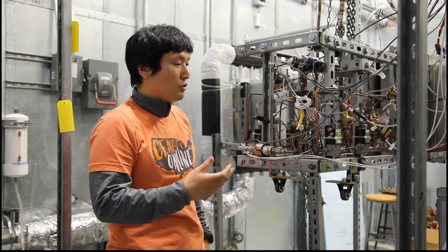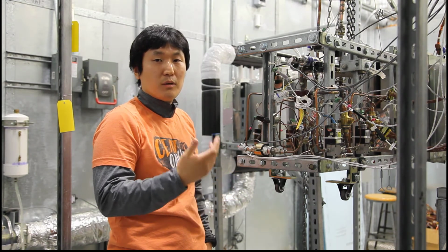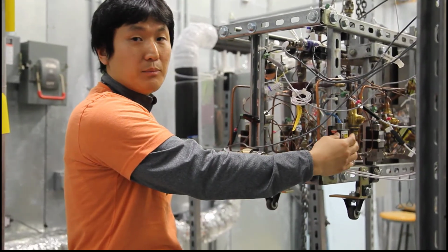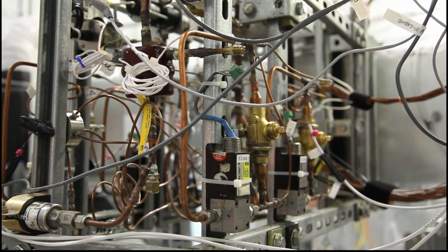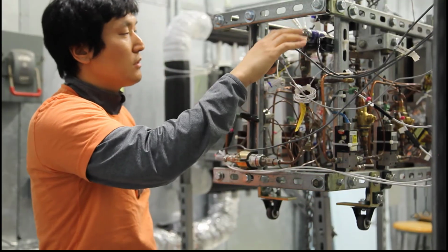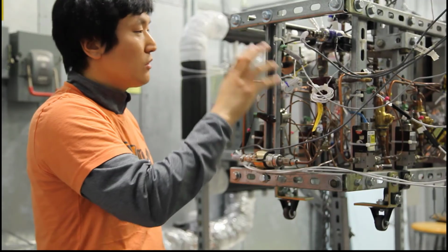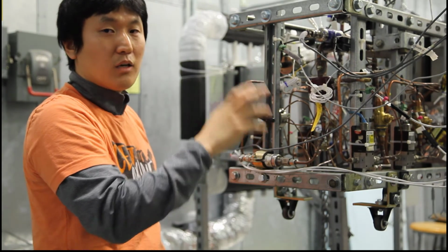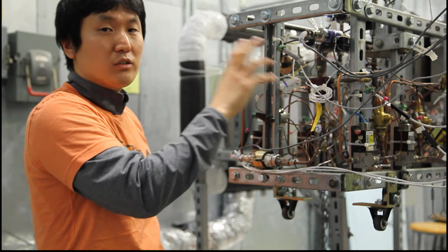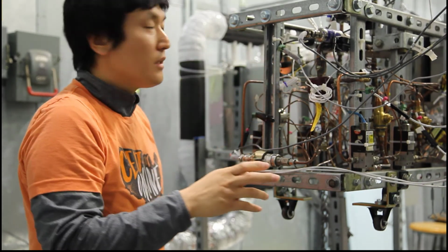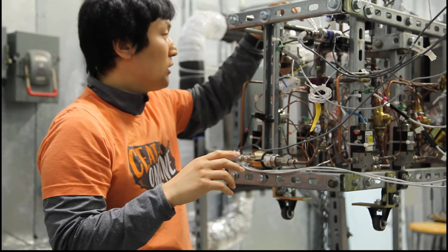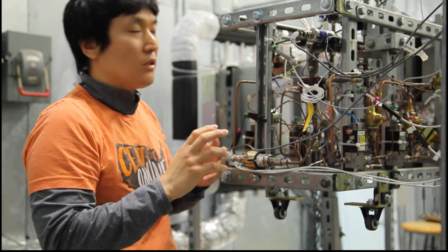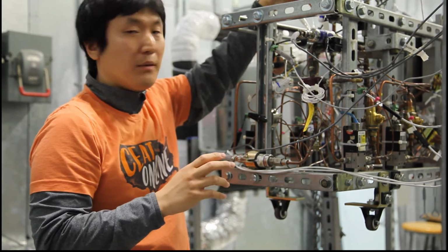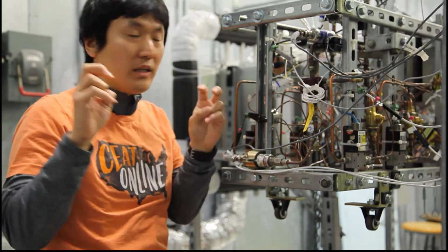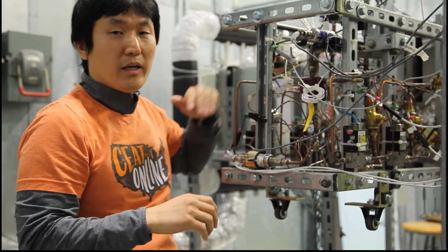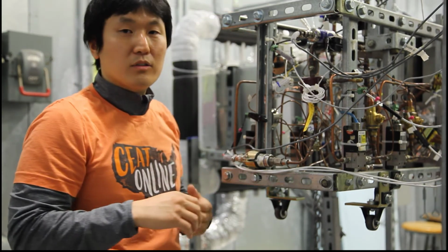And then we have a bunch of instruments to check the pressure and temperature. We have 4 different refrigerant DP sensors to measure the differential pressure, inlet and outlet. And then this one has 2 RTDs, inlet and outlet, to measure the inlet and outlet conditions. Also, likewise, we have 2 different high accuracy pressure sensors at the inlet and outlet. Importantly, we have 2 individual quick shut-off valves, which are placed in the inlet and outlet pipes. So we can quickly isolate this module from the refrigerant loop by closing these shut-off valves at the same time.